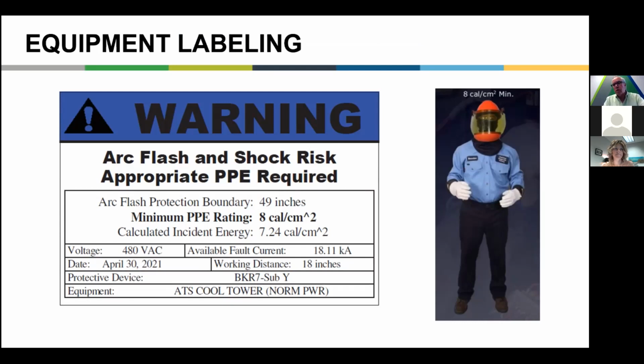Okay, so then as you work up through the ladder of incident energy and a scale of dangerousness, the PPE gets to be more. So this threshold is 8 calories. If it's above 1.2 calories and less than 8 calories, the workers would be guided to wear arc-rated clothing, hand protection, a shield and balaclava. Because at this level of calories, the fireball can surround a worker's head. So a balaclava was added about 6 years ago to protect the neck of the electrical worker. When it gets to be above 8 calories, but less than 40 calories, a full arc flash suit is required.